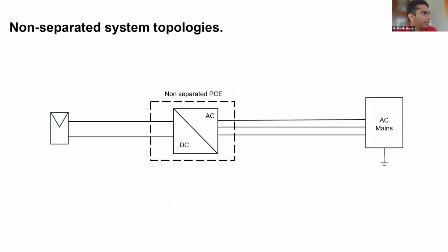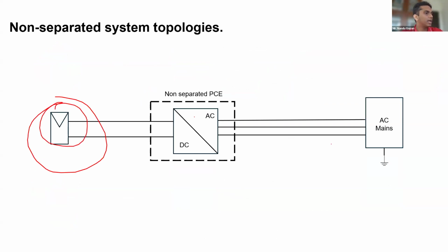Next is non-separated system topology. Non-separated system topology is pretty simple. You will have a PV source and an inverter, and the inverter is not separated. The DC side is not separated from the AC side. You won't have any separation in it. For earth fault protection, this DC side will be relying on the system referencing conductor on the AC side. On the AC side, probably in the discom, there can be a transformer, and the system referencing conductor is done there in the discom. That is what this topology is referring to.